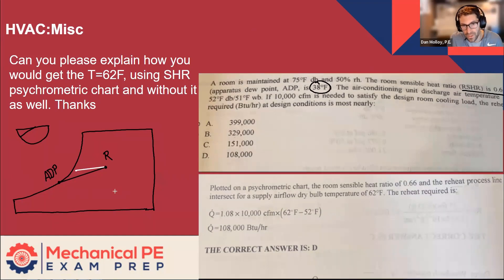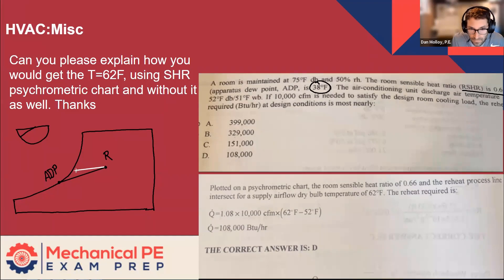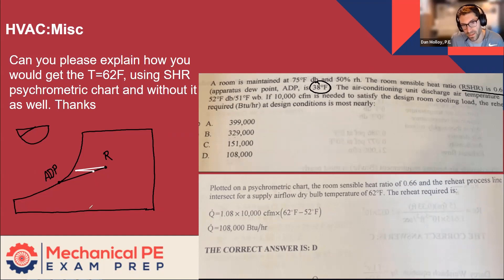That's actually the cooling process that's happening initially, but now we need to reheat. The reason for doing that is to achieve sufficient cooling and a fair amount of dehumidification, but then we're going to do reheat — which means we're going to travel horizontally to the right to get back to the process line we need to be on for the room. So we go from there horizontally back to the right, and hopefully that's a perfectly horizontal line. That's the reheat process.